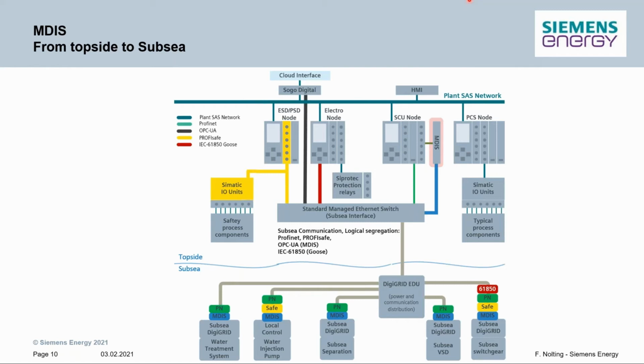And one of the benefits also is that when we use these kind of applications together, we can actually go down to the 10 millisecond area, even on long step outs. That means that we can do anti-surge, closed loop, and so on, really subsea from a topside high-end controller, of course.